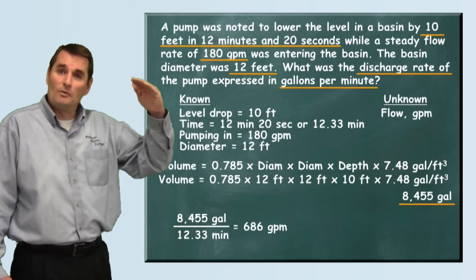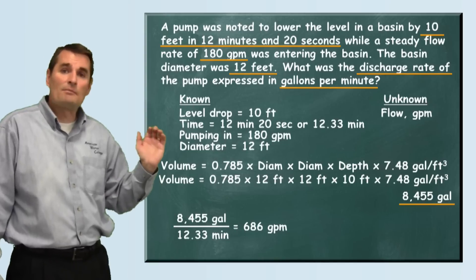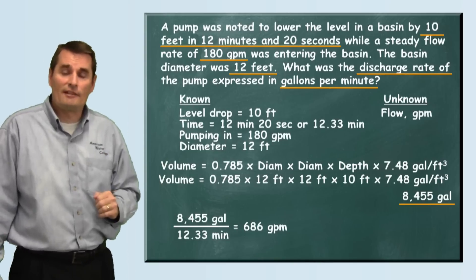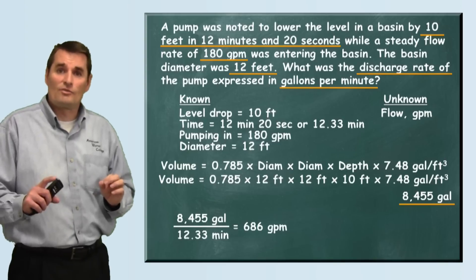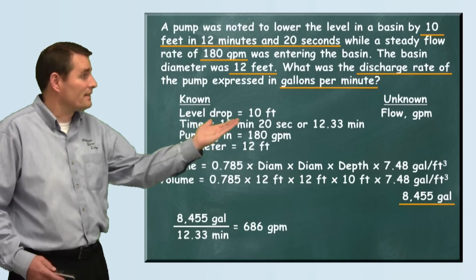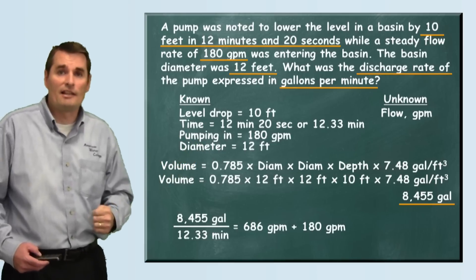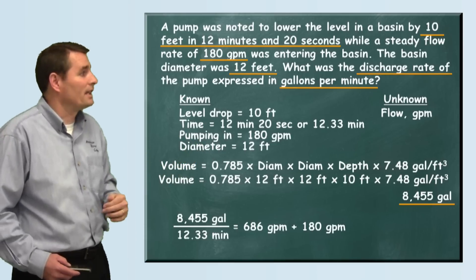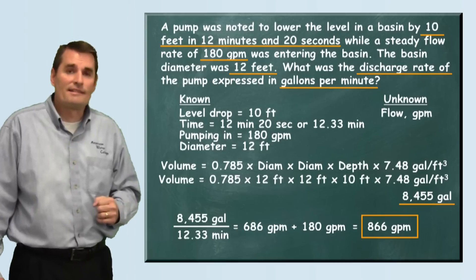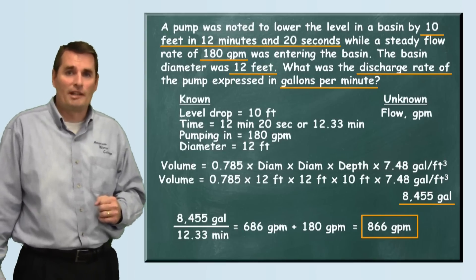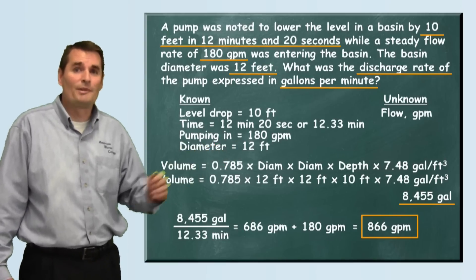Remember, the level was dropping at that rate while 180 gallons per minute were still coming in. So the pump's discharge rate has to be 686 gallons per minute plus the 180 gallons per minute that was coming in, for a total of 866 gallons per minute. And that is how this problem is solved.